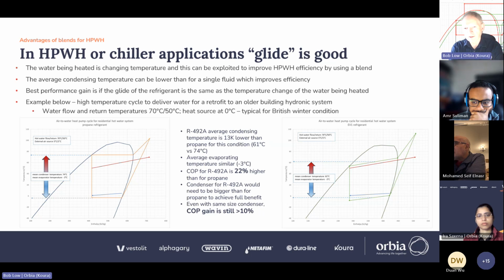In fact, in practice, if you do that, you get added benefits because you will help the compressor. You'll typically reduce the pressure ratio in the compressor, and that means for a recip you'll get a better volumetric efficiency, and for a scroll type compressor, if you get the volume change right, then you'll get a better volumetric efficiency and a better isentropic efficiency. Best efficiency gain on Lorenz cycles, you match the temperature change of the fluids.